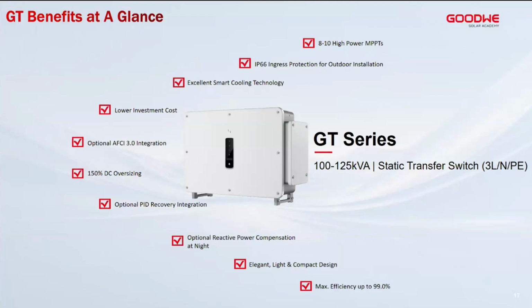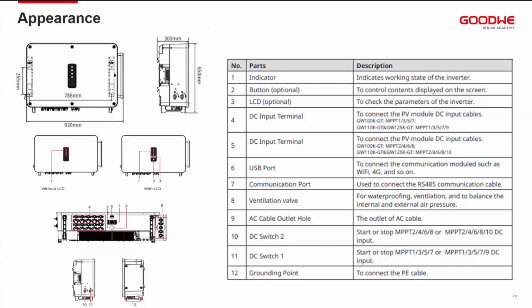Now the product itself is elegant and light, and high power as well, as you can see. We've moved the DC switches from the bottom of the inverter to the side, so it's easier to reach, and you can easily identify which ports the DC MPPTs are on. You don't need to bend down to look under the inverter itself. Efficiency is quite high, up to a maximum of 99%. These are the unique features of the GT series, making it the top product of the C&I market. I will show you how to connect this on-grid inverter with a hybrid inverter to make a microgrid later on, as we look into the application scenarios.